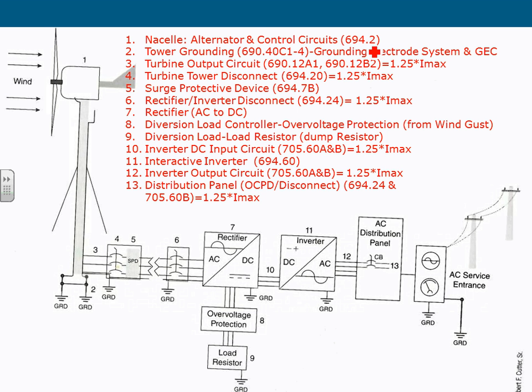You have to ground the tower, and one of the most important reasons why we ground the tower is, of course, lightning. They call it an auxiliary grounding electrode system. Like any other generator, the code requires you, even if you have a generator outdoors, to have a grounding electrode system right by the generator. So this is really nothing fancy.